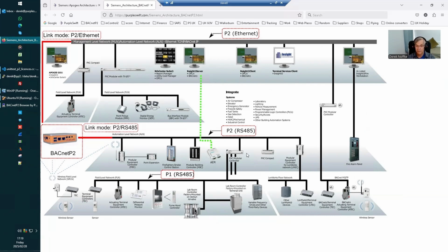The other thing is, if a panel fails, then you've got these FLN devices with all the TECs that suddenly become orphaned. And we have a device called an IP modem that we can pop in there, and it'll pick up the P1 networks and bring all these devices back into our gateway. So we can help in terms of upgrading the site and minimizing the downtime.